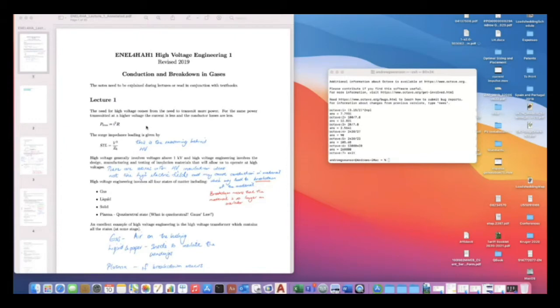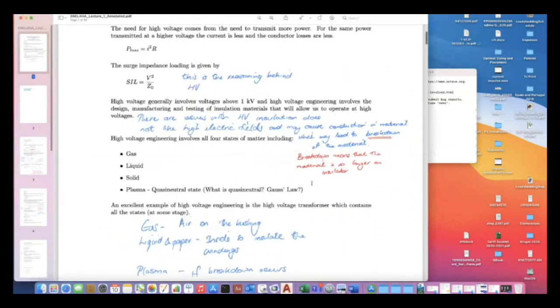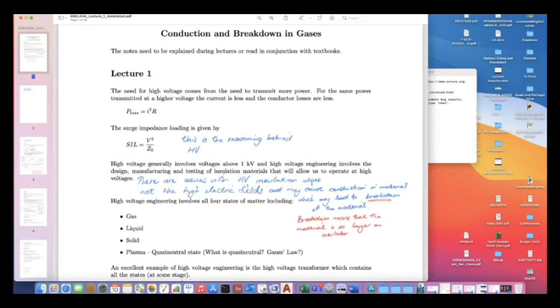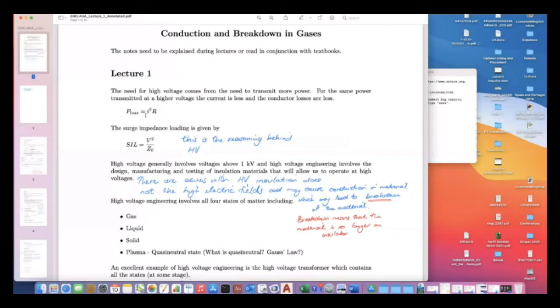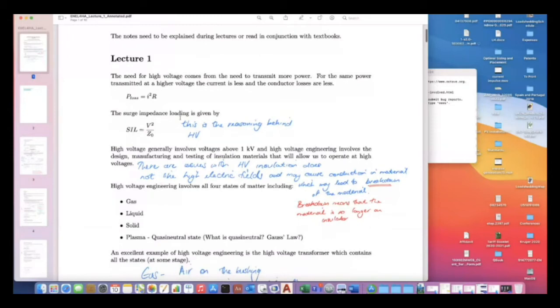Right, so the need for high voltage comes from the need to transmit more power. We know that for the same power transmitted at a higher voltage, the current will be less, and therefore the conductor losses are less. And we know that equation quite well, I squared R. R would be the resistance of any of those overhead conductors, and I would be the current through it. The surge impedance loading is something that you may have done in power systems. So you can transmit more power if the voltage is higher. You could have a line with the same impedance, and if you keep on increasing the voltage, you can increase the power transmitted on the line.